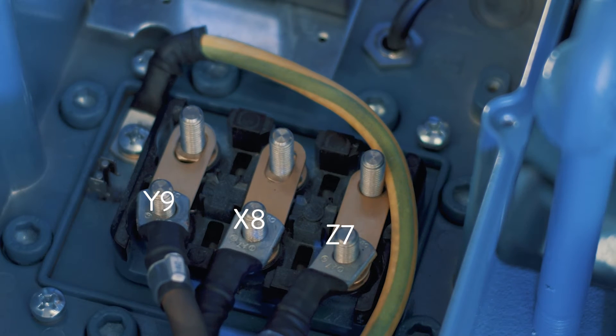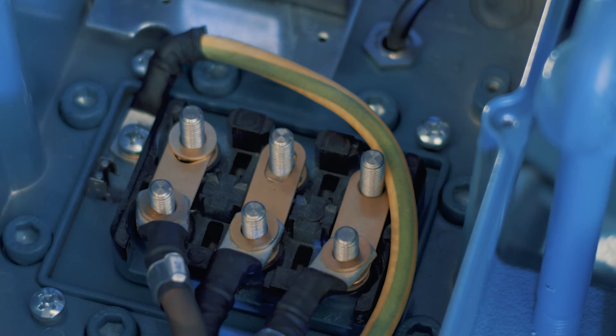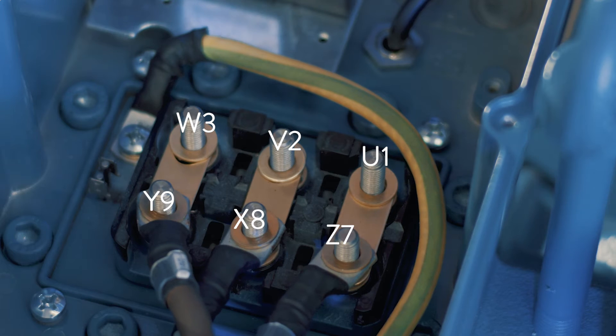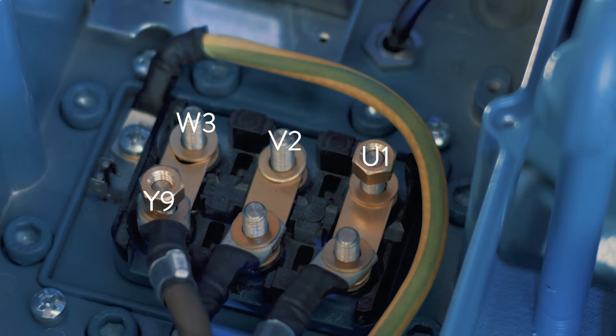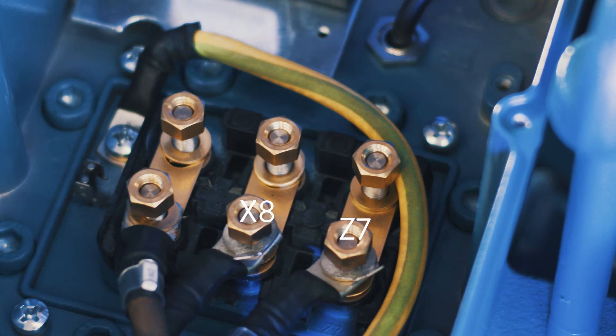Place the set of cables inside the drilled hole. Place the three cables on the three pins Z7, X8, and Y9. Take six washers and place them on each pin. Take four nuts and place them on the four pins Y9, W3, V2, and U1. Take the two eyelets for the screw-on wiring and place them on the two remaining pins X8 and Z7. Place the two remaining nuts on top of the two rings just placed.